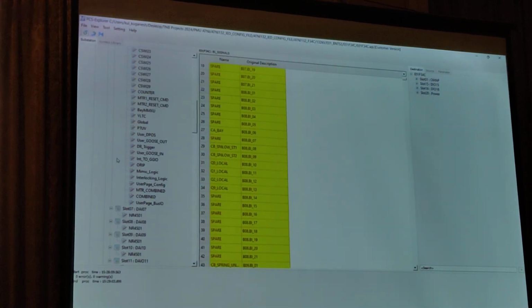Oh. Kalau kita terlupa ke, kalau termiss ke, then we don't know what have been changed. So that's why kita tak try ubah banyak. Kita try to maintain yang mana boleh maintain, and then try to follow it lah. Then easy for the troubleshoot. Because we have a BCU yang 100% working properly, already commissioned, already tested, and then you are replicating another one. So as long as you follow the most of the things same, you will find it easier to troubleshoot lah. Because it should work as similar as the live BCU supposedly.